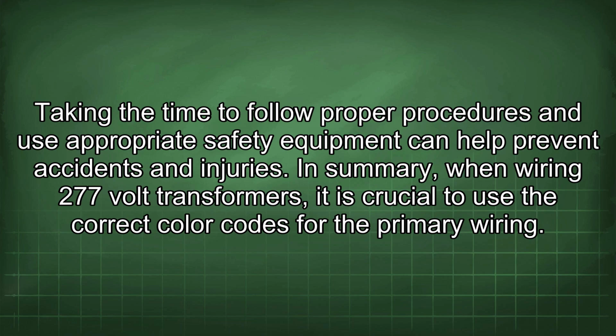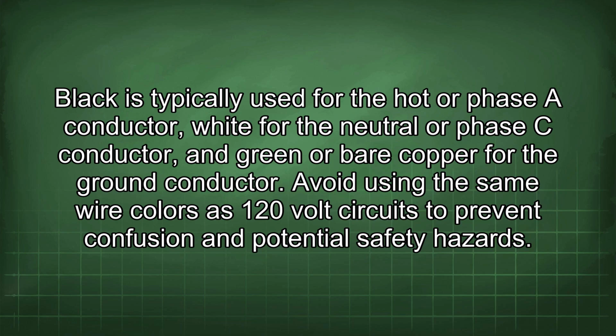In summary, when wiring 277-volt transformers, it is crucial to use the correct color codes for the primary wiring. Black is typically used for the hot or phase conductor, white for the neutral or phase C conductor, and green or bare copper for the ground conductor.